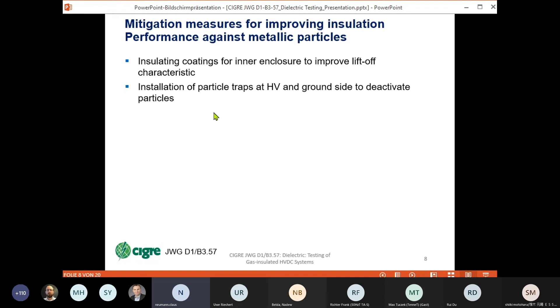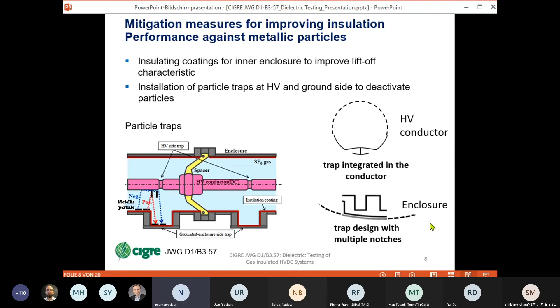The two main characteristics can be observed at negative polarity, the so-called firefly phenomenon, and at positive polarity, the bouncing motion. And we have to apply mitigation measures for improving the insulation performance against metallic particles, that is insulating coating, and installation of particle traps. You have seen this particle trap, which is mainly applied in Japan, but other traps are also applied here, a trap integrated in the conductor, or a trap with multiple notches integrated at the enclosure side.